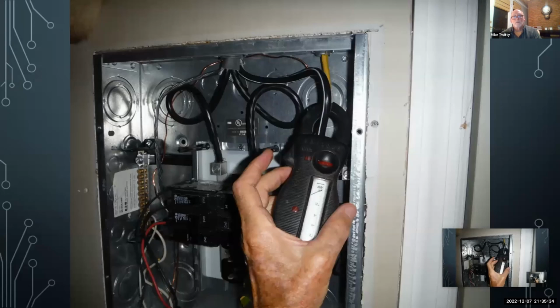Okay, I put a load on this panel. This is just a little experiment I did to show some things. Put a load on it. This is the service neutral. It's about a 16 amp load on this 20 amp branch circuit. That's the only thing on right now. And that's showing that the neutral is carrying that 16 amps back through the feeder, back to the supply breaker.